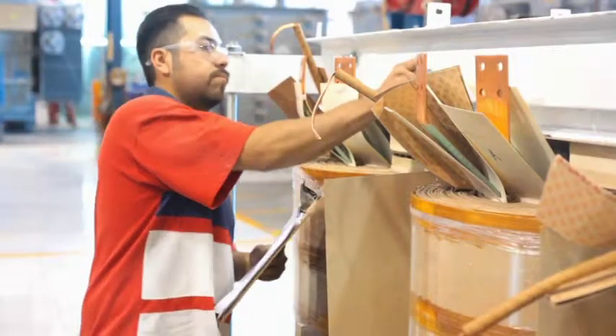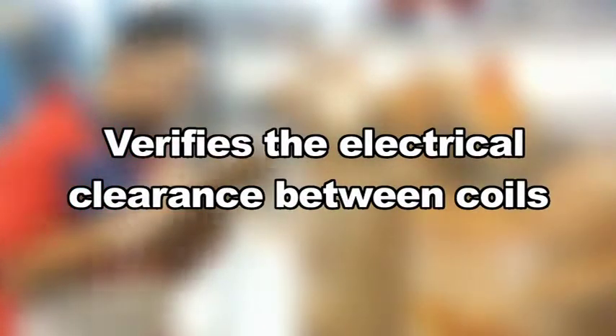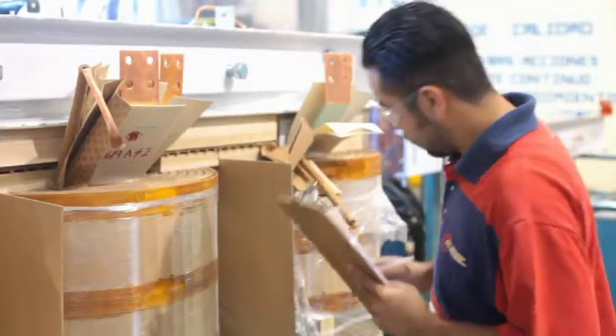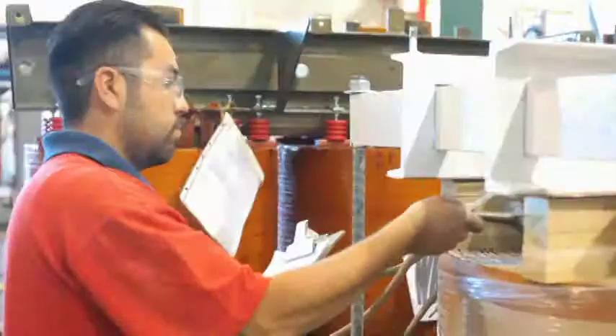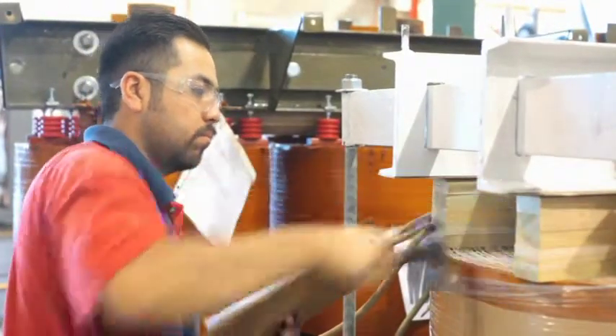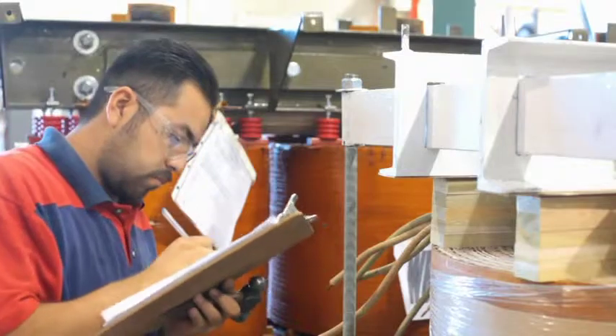The inspection process in the core and coil assembly verifies the electrical clearance between coils is met, complying with the minimum required by engineering and design, since this minimum distance ensures the long life of the insulation of these coils. Also ensures that the coils are properly seated and secured through the metal hardware.